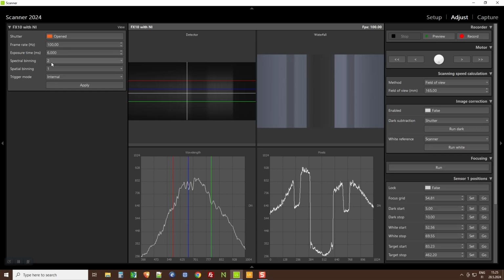With this camera, with the FX10, the light is actually dispersed over 448 bands, but the optical resolution does not justify having too fine a sampling. So we actually recommend using a spectral binning of 2. It means that you don't have 448 bands, but effectively 224. And we recommend that because then you can improve your signal-to-noise ratio.